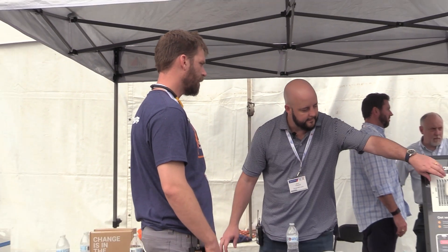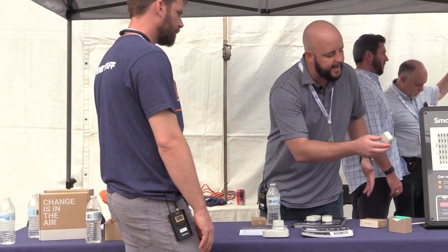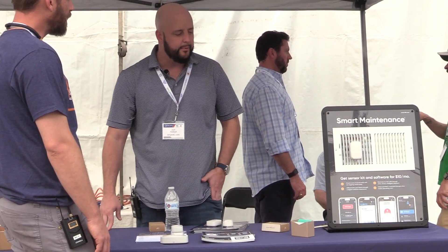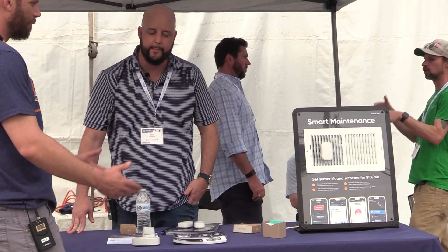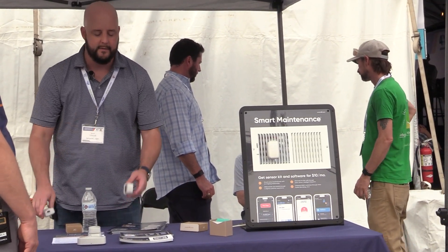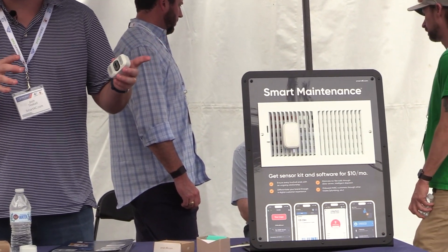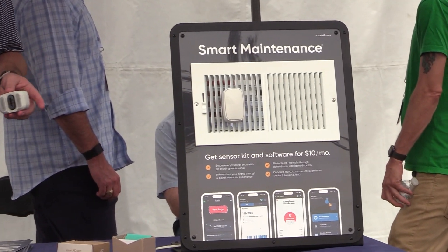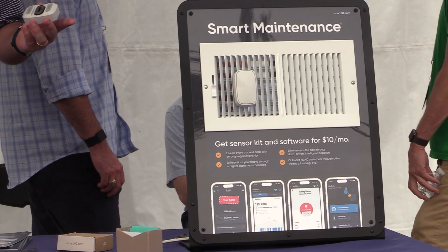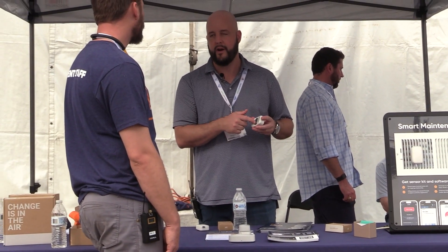You said low cost and easy installation — show me the installation. There are a couple of accessories just in case, but many applications it's as simple as putting the magnet sensor on there. That's the comfort sensor. Then one goes in the return vent — that's our filter sensor — and that gives us the vent-to-vent delta T split, the same places where the probes go for MeasureQuick.